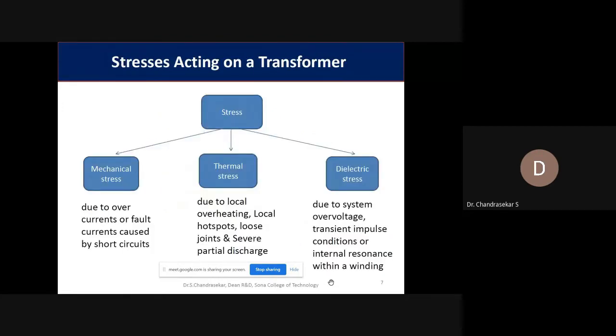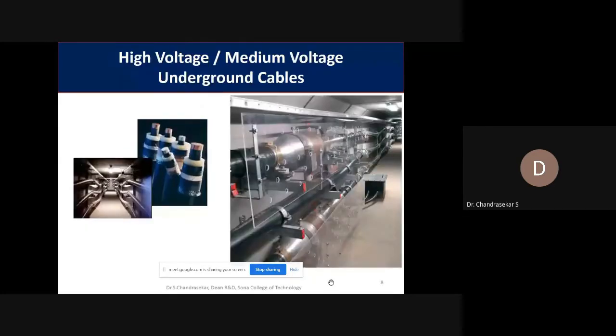There are so many stresses acting on a transformer in day-to-day life: mechanical stress, thermal stress and dielectric stress. Mechanical stress is mainly due to overcurrent and fault currents from short circuits. Thermal stress is due to overheating and local hot spots. Dielectric stress is mainly due to overvoltages: switching overvoltage, transient overvoltage and lightning impulse overvoltage, or due to any resonance within the winding. All these stresses act on the transformer and slowly degrade the insulation used inside it.